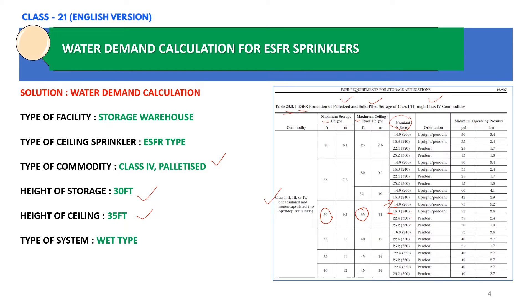Here we are considering a K factor of 14.8 with upright or pendant orientation. Since this is a warehouse, we consider upright sprinklers. The minimum operating pressure for this sprinkler is 5.2 bar, which converts to 75 PSI.